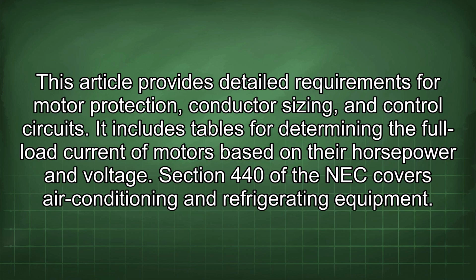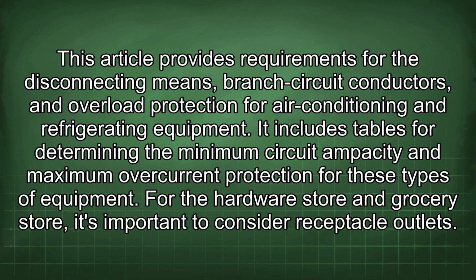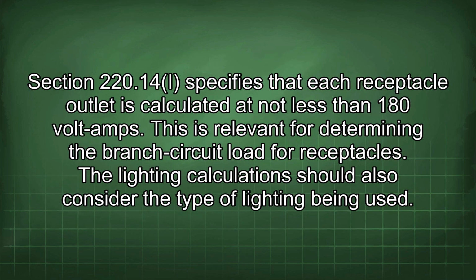Section 440 of the NEC covers air conditioning and refrigerating equipment. This article provides requirements for the disconnecting means, branch circuit conductors, and overload protection for air conditioning and refrigerating equipment. It includes tables for determining the minimum circuit ampacity and maximum overcurrent protection for these types of equipment. For the hardware store and grocery store, it's important to consider receptacle outlets. Section 220.14 specifies that each receptacle outlet is calculated at not less than 180 volt amps. This is relevant for determining the branch circuit load for receptacles.